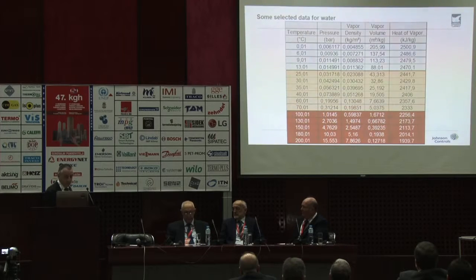Just to make a few extra comparisons here, in the second row you have the pressure, and you can see 0.006 bar at about the triple point, where 6 degrees is not much higher. But when we get up to, for example, 130 degrees, we are at the phenomenal pressure of 2.7 bar. It is over, so it will be covered by the PED. But as long as we stay down in the normal air conditioning area, we are not covered by PED, which is a cost reduction.